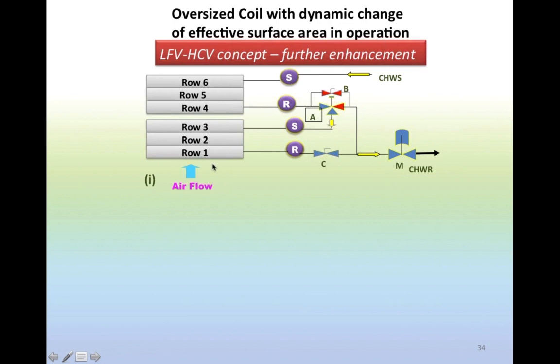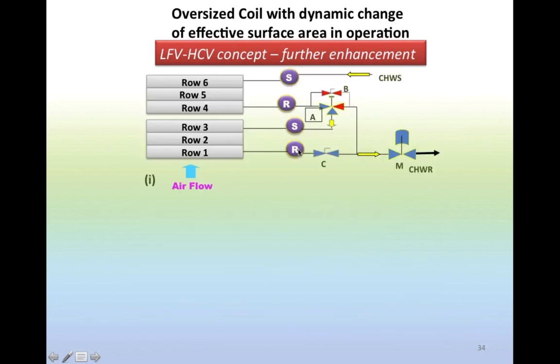Here you see a 6-row deep coil, the same one that I discussed with you in the table earlier. We got the counterflow arrangement, airflow from the bottom to the top of the screen, and the chill water supply to the supply manifold going to rows 6, 5, and 4. And just a little change that I'm going to do here, I collect the water after row 4 into a return manifold, and then I got a little bit of a manipulation of the flow of the chill water. I feed it back into row 3 through another supply manifold, 3, 2, and 1, collected in this manifold, and we have the modulating valve here.